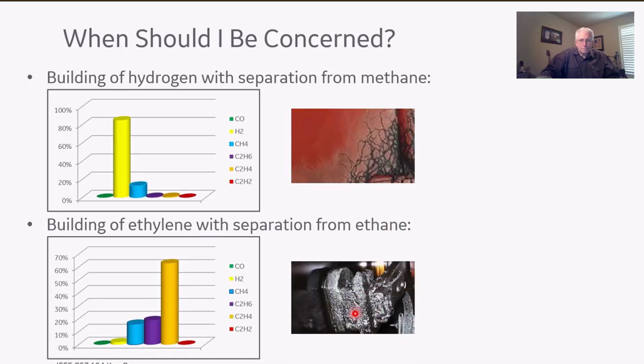And that coke looks something like this, in its worst stages, by the way. This is a good example of a coke buildup. Now, it's been there a while. It's in pretty bad shape. It's not pretty to look at, and every bit of that had to be replaced. But you see this a lot of times on de-energized tap changers. That's the tap changer that is operated with the transformer out of service, for those that may not know. And there's a wheel or a dial or a lever on the side of the transformer that should have a lock on it. While that transformer's in service, that should be locked down.